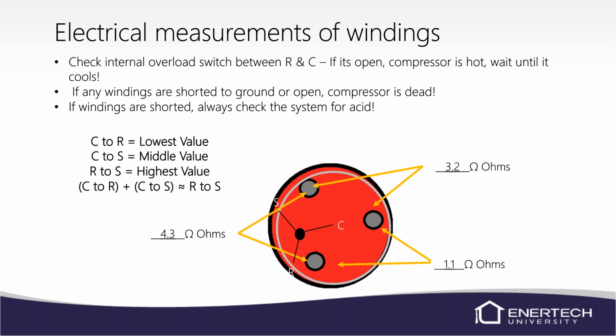Normally, your common to run and your common to start, those two readings, so 3.2 and 1.1, will normally equal or be very close to the highest value, or your run to start. So you can see here, 3.2 and 1.1, that's 4.3 ohms. So that's what we're seeing on the run to start. Now, it may not work out exactly, but it's going to be pretty close. And your resistance should be minimal.